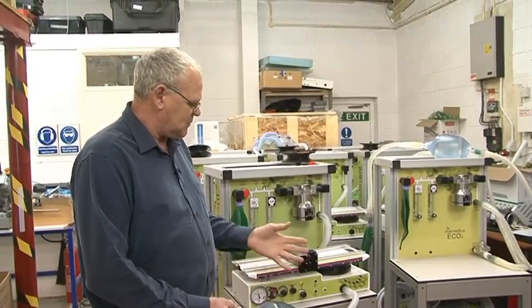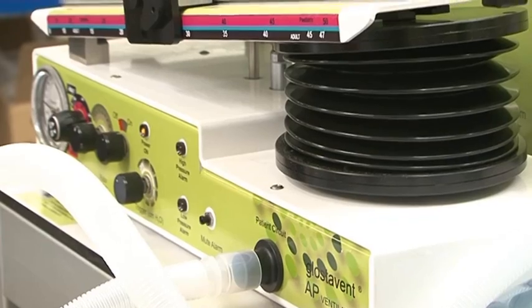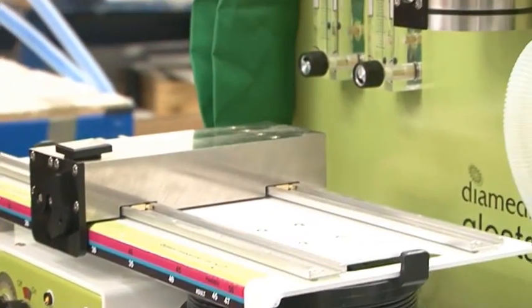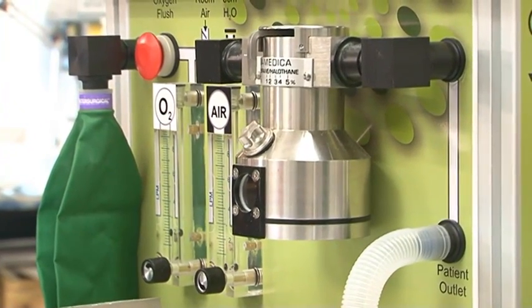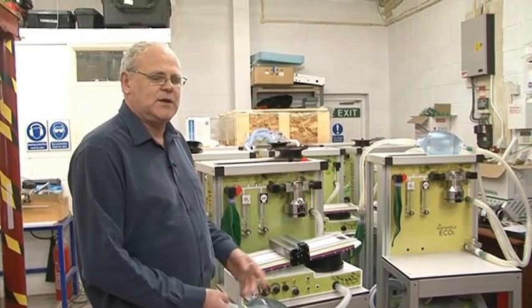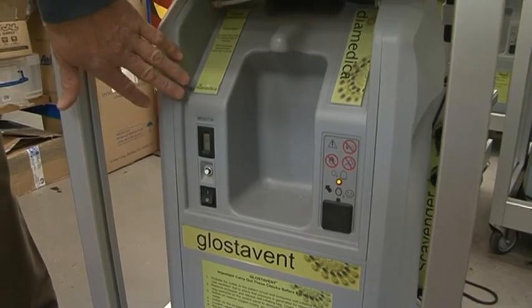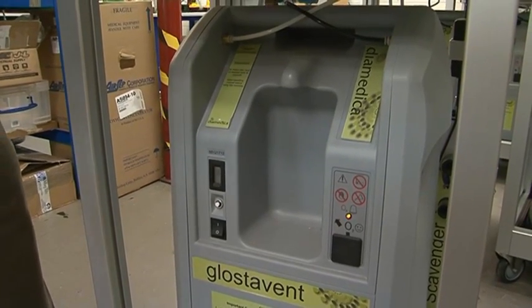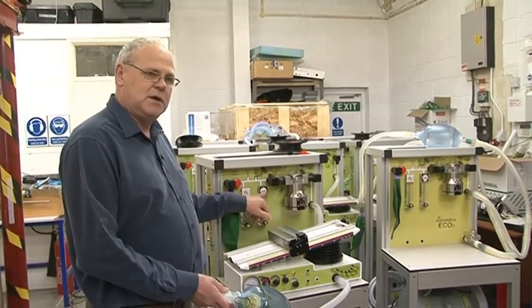This is our principal anaesthetic machine, the Glostavent, currently working in over 45 countries. We have a battery support on the back and a voltage stabiliser for the electrical conditions we are likely to be operating in. We have an oxygen concentrator in the bottom that takes atmospheric air and gives us medical oxygen and medical air.